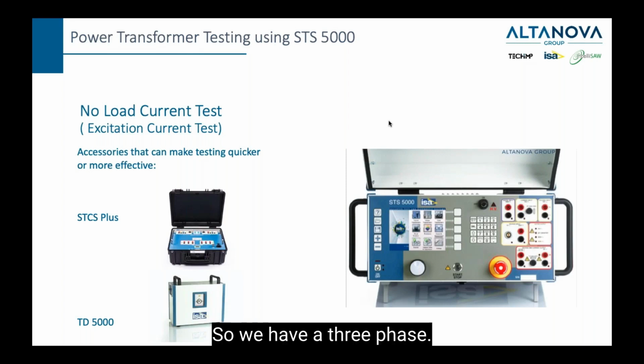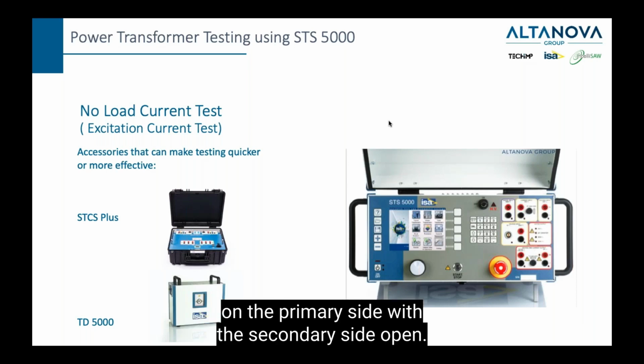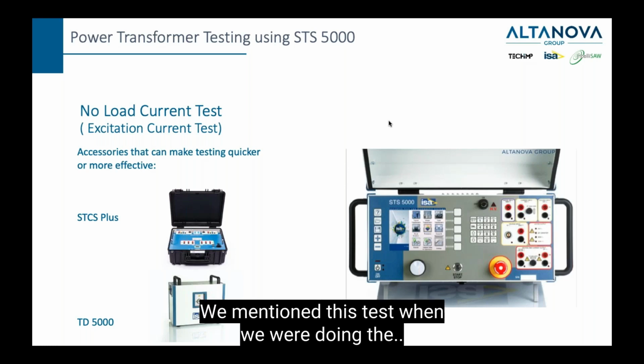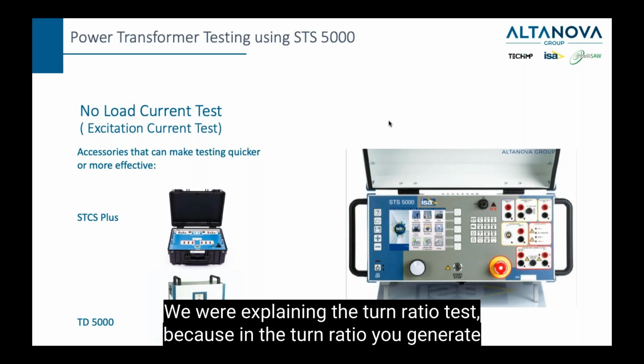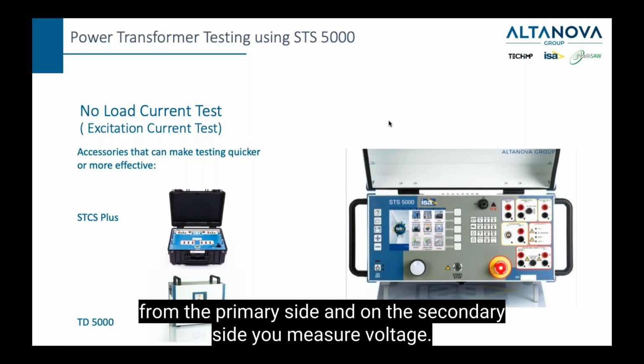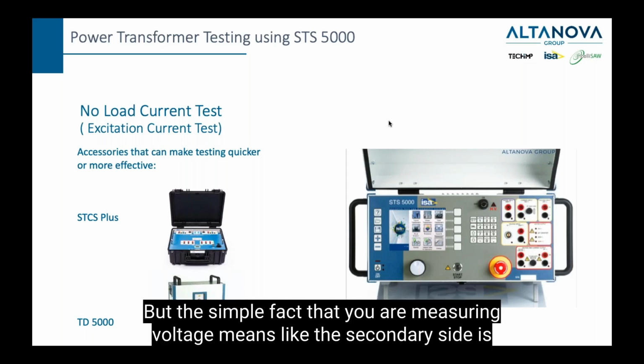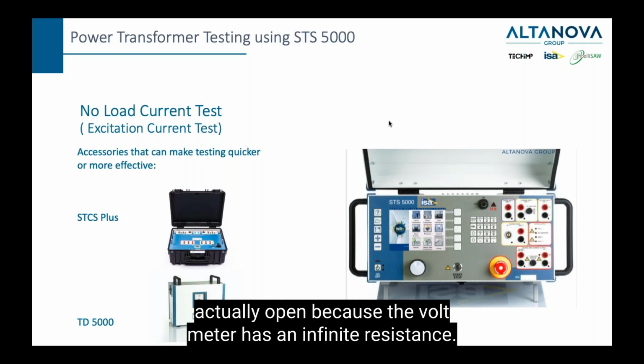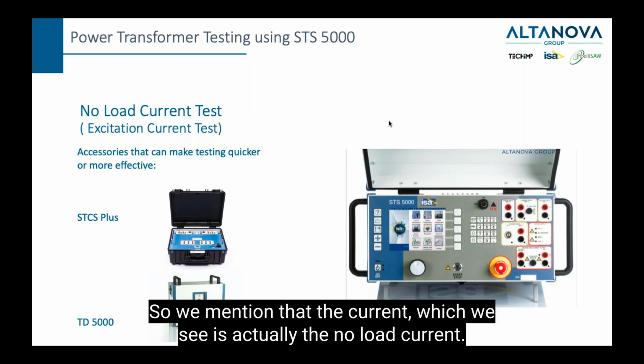So we have a three-phase generator, and what they do is they generate on the primary side with the secondary side open. We mentioned this test when we were explaining the turn ratio test, because in the turn ratio you generate on the primary side, and on the secondary side you measure voltage. But the simple fact that you are measuring voltage means the secondary side is actually open, because the voltmeter has an infinite resistance. So we mentioned that the current which we see is actually the no load current.